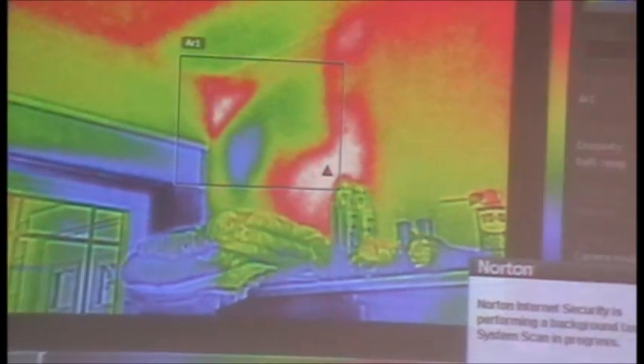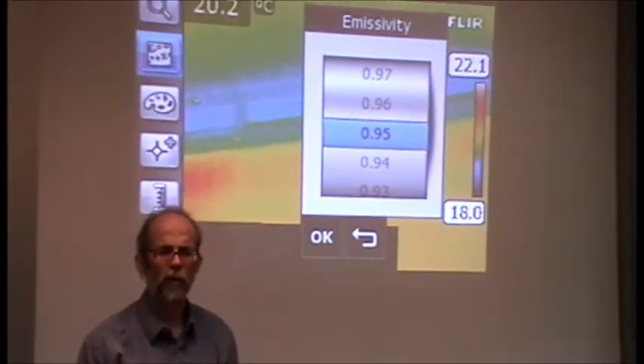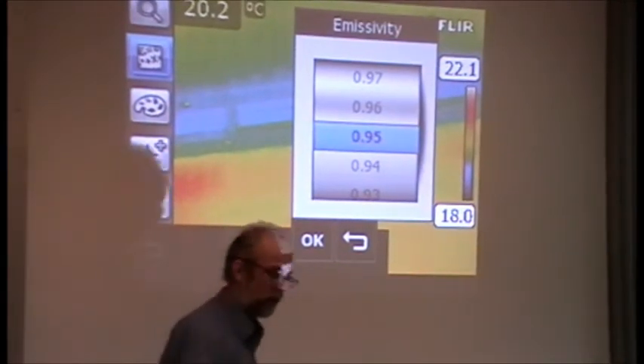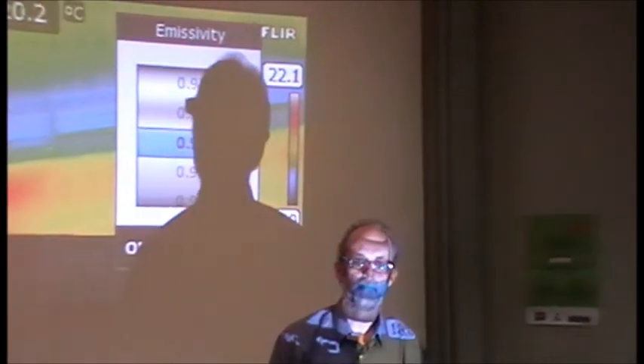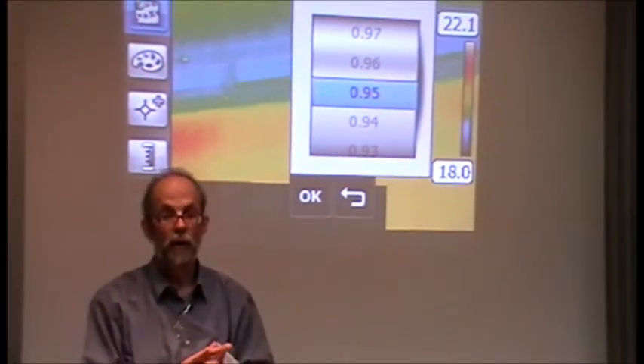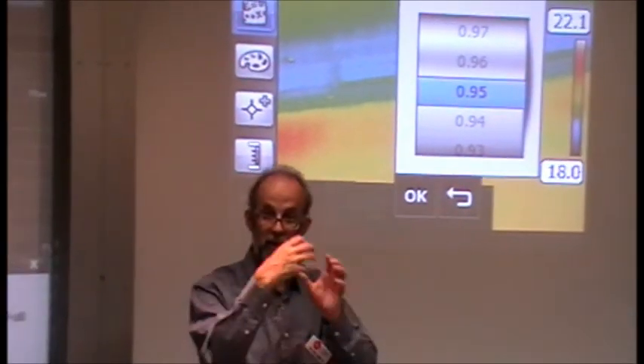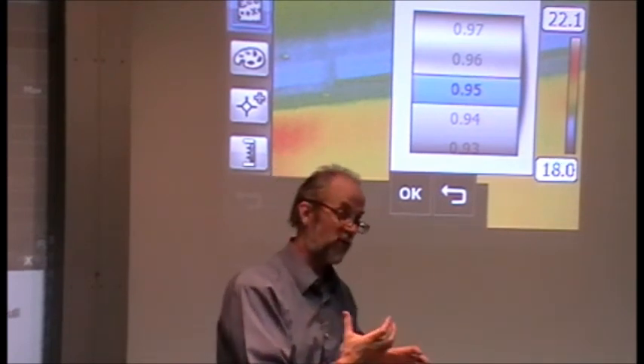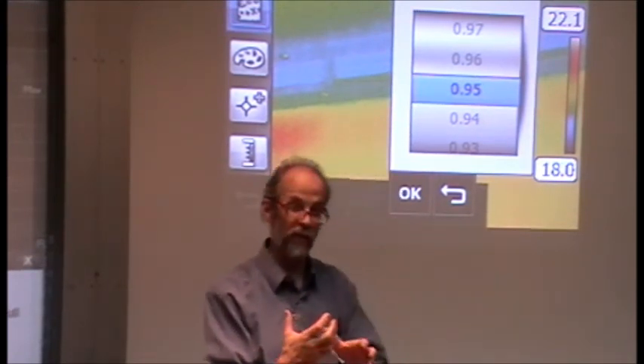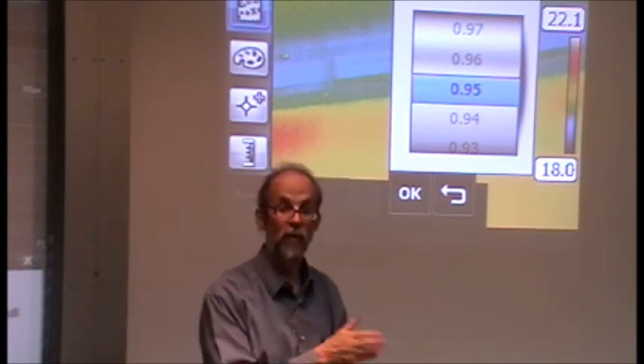Ice, I think, is also very good, but snow is bad, from memory. I think that's right, it might be the other way around. Stone and stuff like that? Stone itself is a non-metal and tends to have a high emissivity. No problem. Even if it's a polished stone, it is still quite high. We don't have one here, but a glazed ceramic cup, nice and bright and shiny, has an emissivity of about 0.85 to 0.9, depending on what it is. It's certainly not down where the metals are.